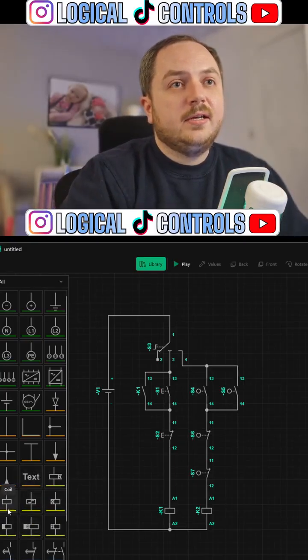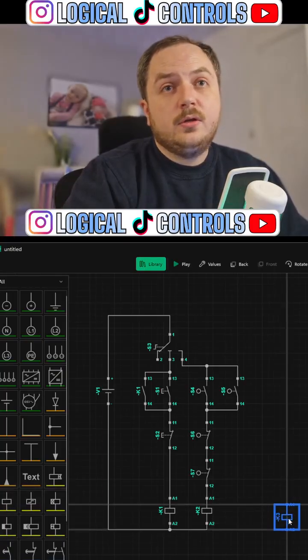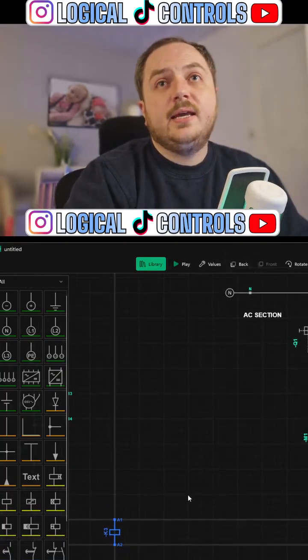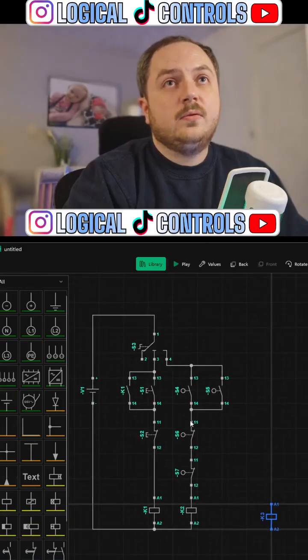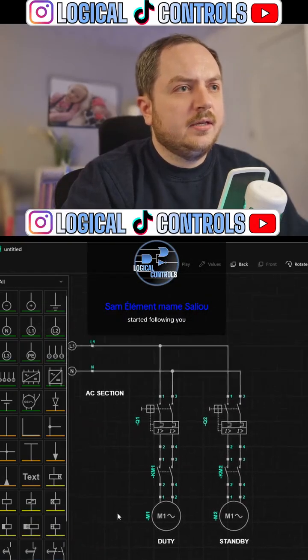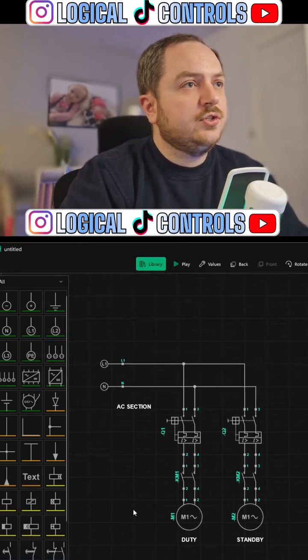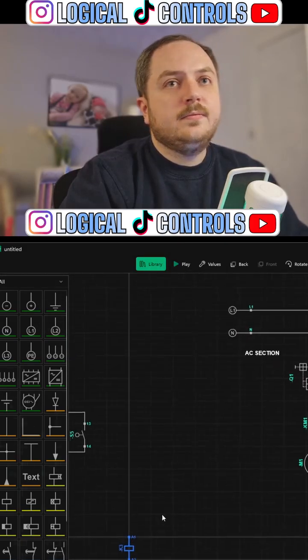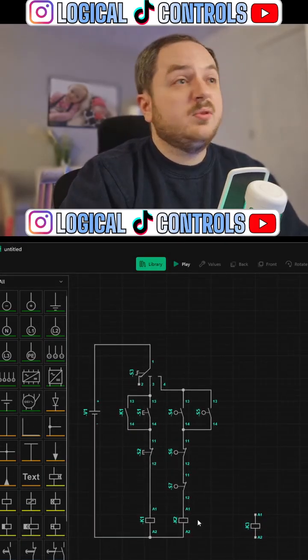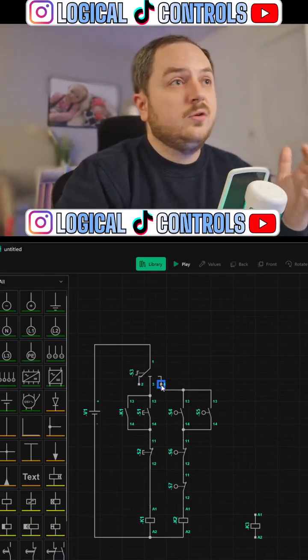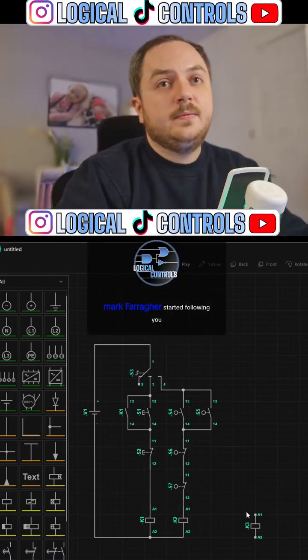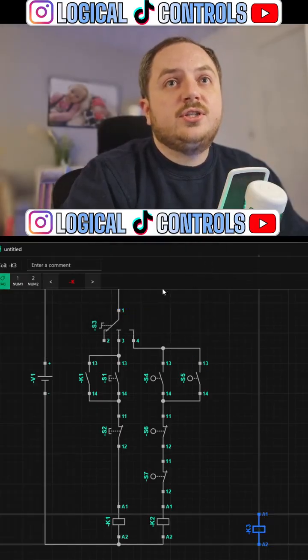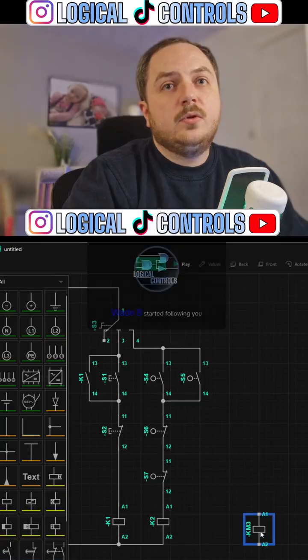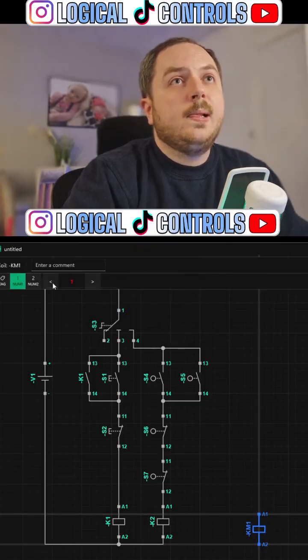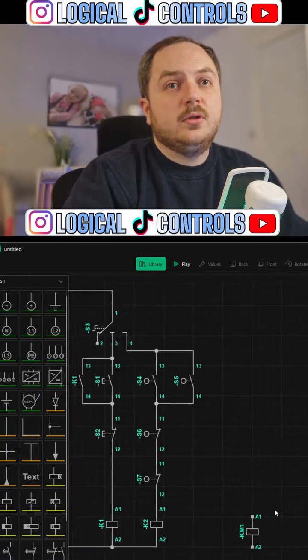So let's add our contactor coil, which won't be K3, it will be KM1, I think we called it. Yeah, KM1. We've got an AC section, a DC section if you're just joining. Yeah, the HOA switch - that's pretty much what I've got. I've got off mode, hand mode, auto mode. That's what we've built. So let me just change this value to KM1. No, it's gone to 3 for whatever reason. We want KM1, that's right, okay.